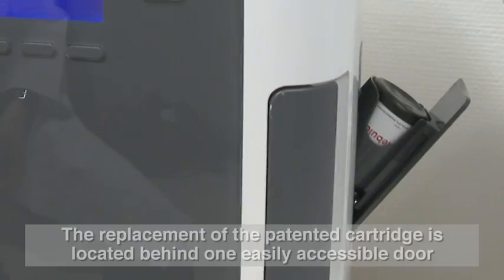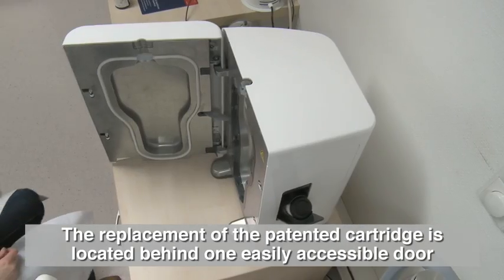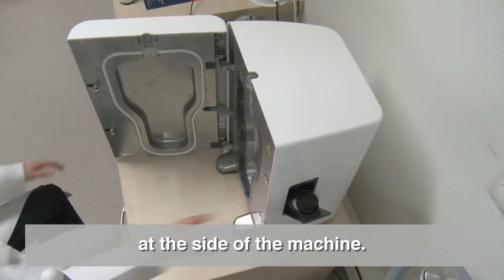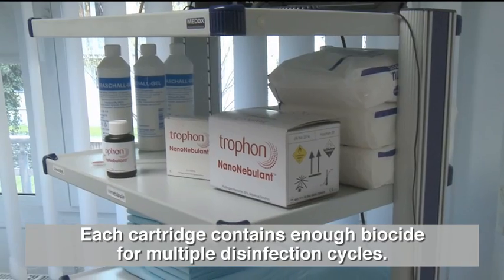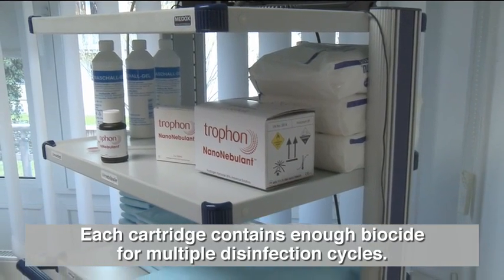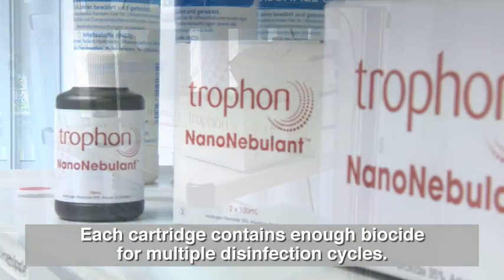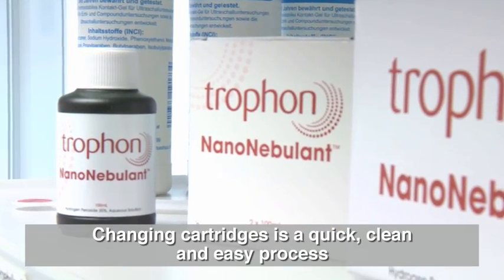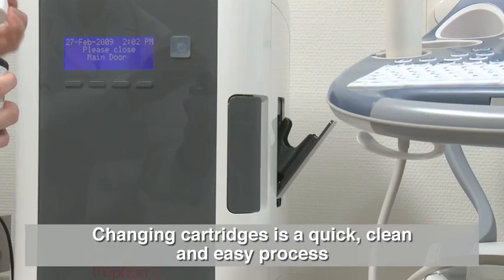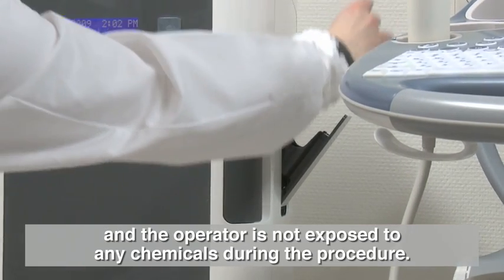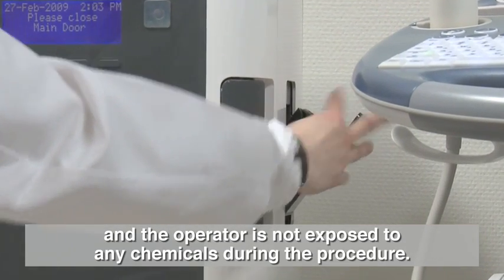The replacement of the patented cartridge is located behind one easily accessible door at the side of the machine. Each cartridge contains enough biocide for multiple disinfection cycles. Changing cartridges is a quick, clean and easy process, and the operator is not exposed to any chemicals during the procedure.